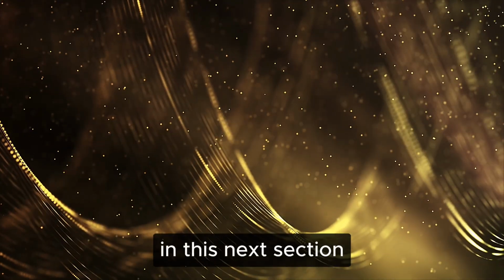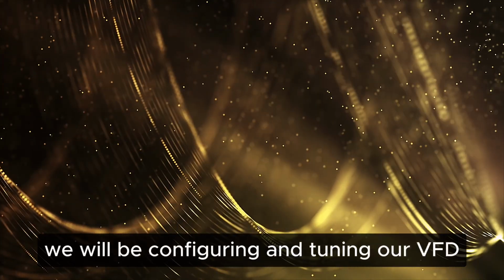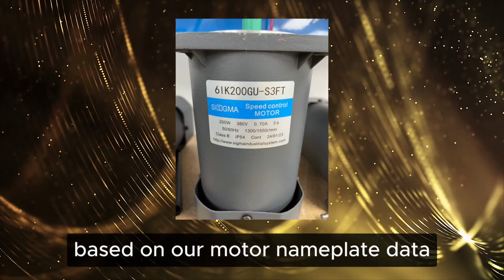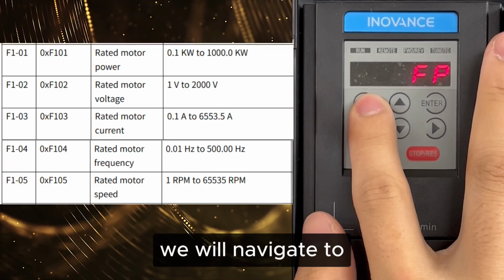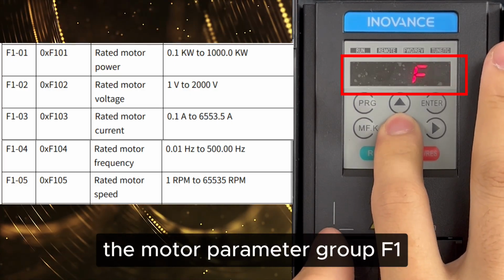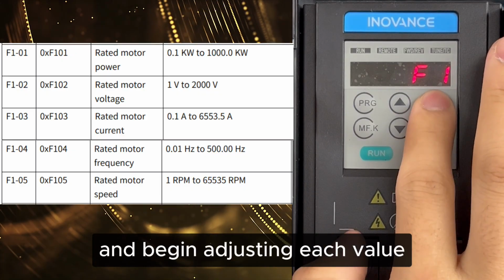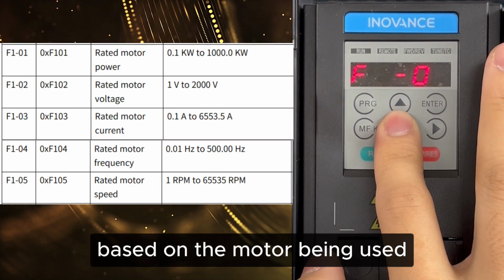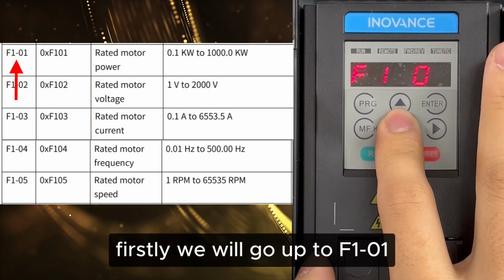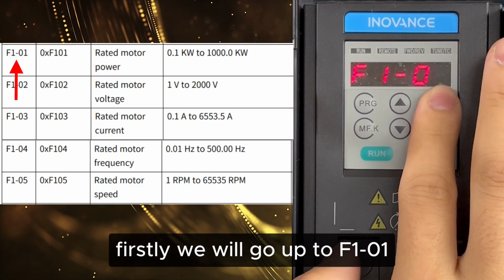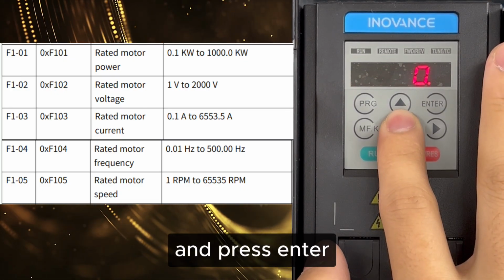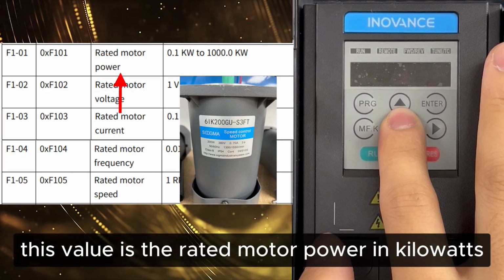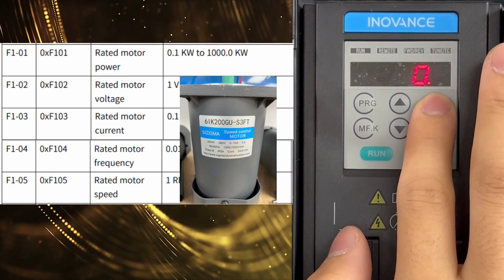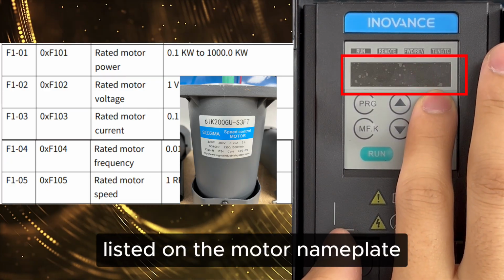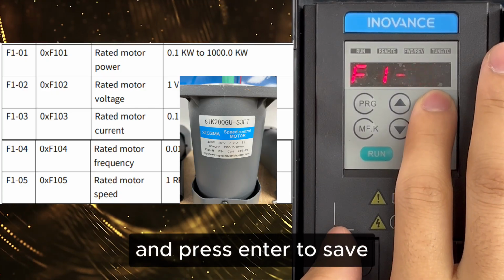In this next section, we will be configuring and tuning our VFD based on our motor nameplate data. We will navigate to the motor parameter group, F1, and begin adjusting each value based on the motor being used. Firstly, we will go up to F1-01 and press Enter. This value is the rated motor power in kilowatts. Change this to the value listed on the motor nameplate and press Enter to save.